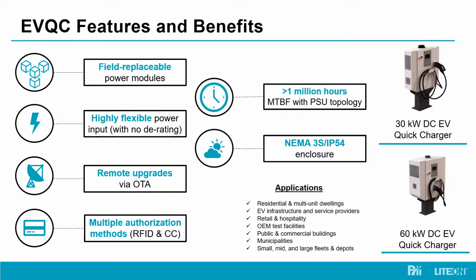I mentioned that you can take a number of different input voltages, 240 single phase all the way up to 480 three-phase Y, and we're able to accept those input voltages with no derating. There may be other manufacturers that can handle different input voltages, but you may lose some of the power you actually purchased. We're able to accept all those voltages without losing any of the power you purchased, unlike some of the other ones you may be familiar with.